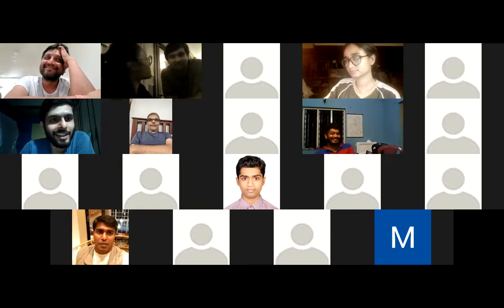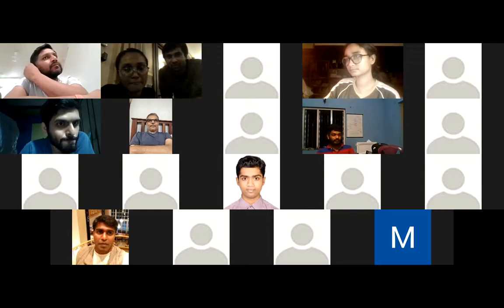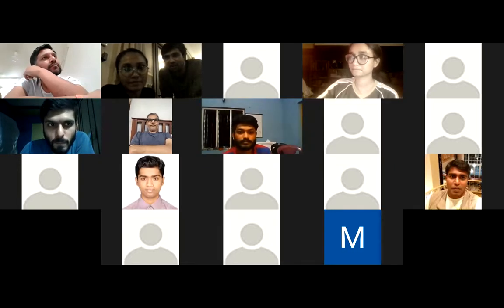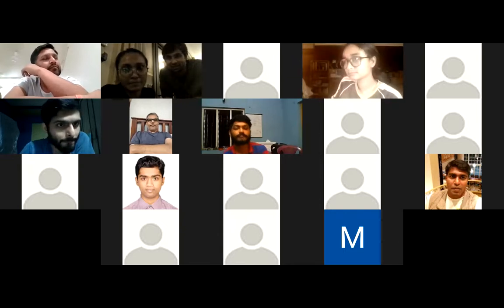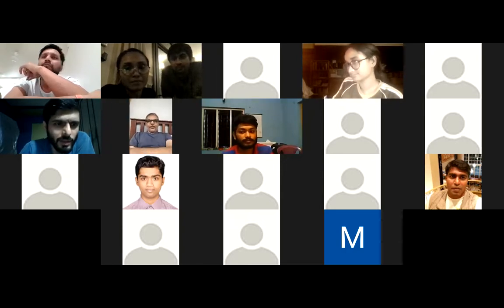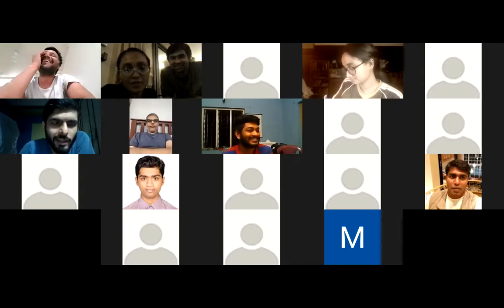Actually, that's one of the things that we also learned, that the Chinese ones that are coming in, because the humidity level in China is very, very low. When they come to India, they don't actually have all the dehumidification parts, which means that most of them are malfunctioning in certain parts, and all the zeolites are becoming clunky very soon. That's going to reduce the oxygen output very soon. So they won't last very long, these devices. Most of them are dead on arrival, actually. That's exactly what we're hearing on the ground as well.